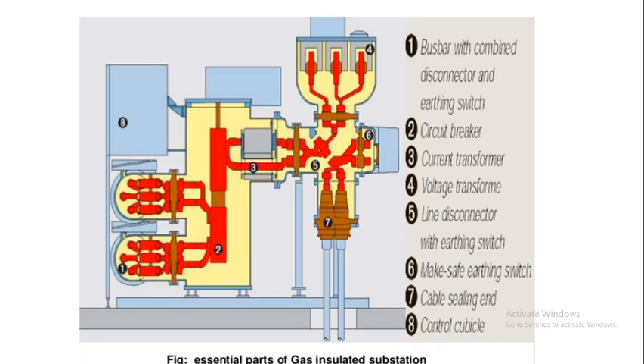So this is a pictorial representation giving you the essential parts of a gas insulated substation. So here you can have a look. This is a complete gas insulated substation, and we are showing you the internal structure. The different parts are numbered, and each number represents an equipment. So this is the first equipment: the bus bar with a combined disconnector and earthing switch. First we have the bus bars, where the incoming lines will be connected. These are the bus bars that you can see here. The second is the circuit breaker. This is a complete circuit breaker assembly consisting of a fixed contact and a moving contact. This is the circuit breaker, number two.